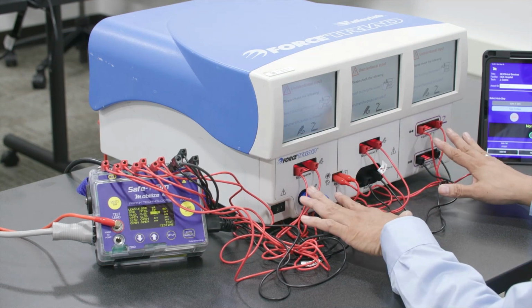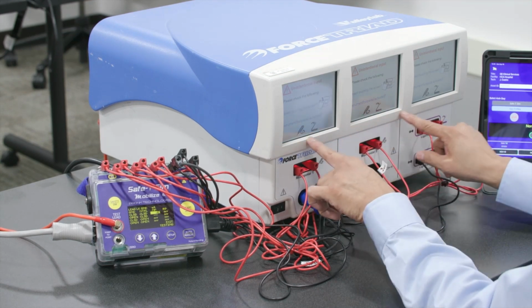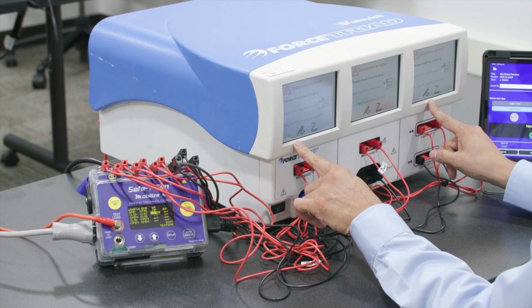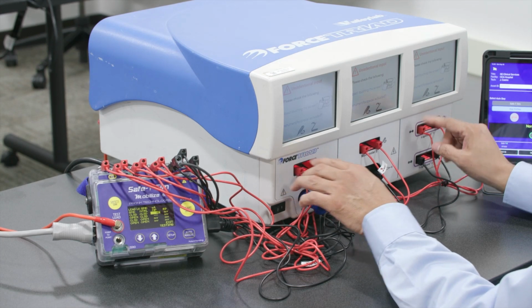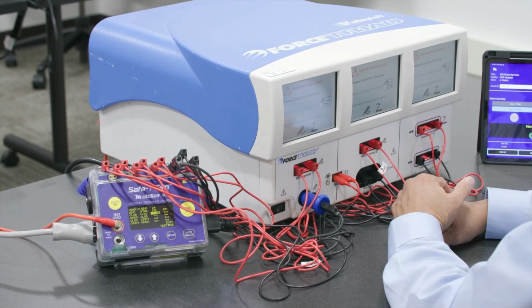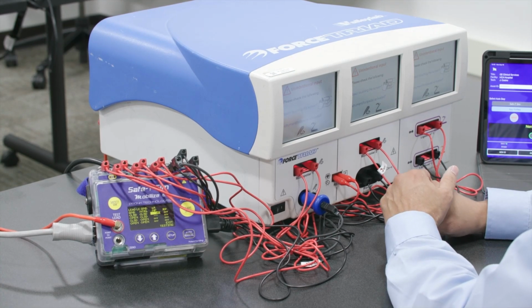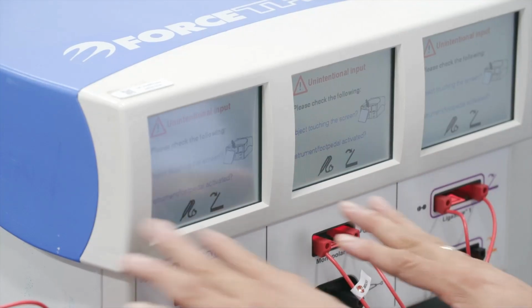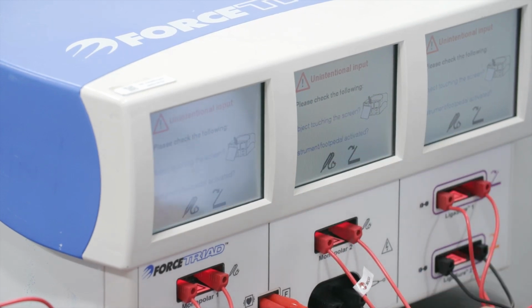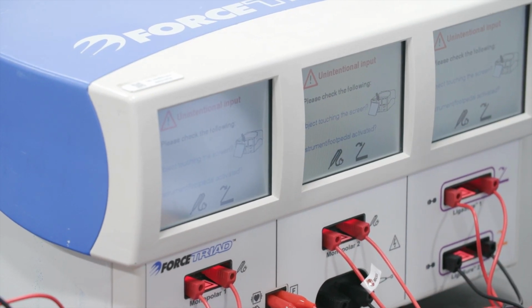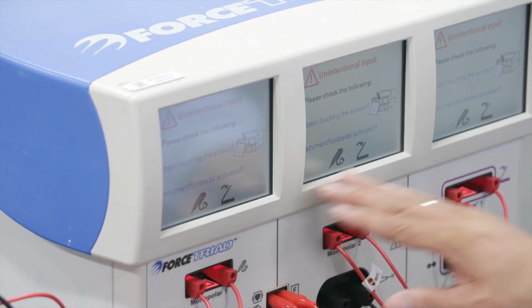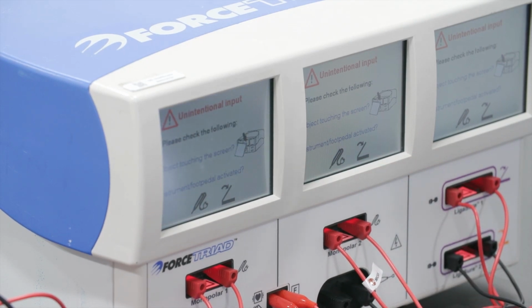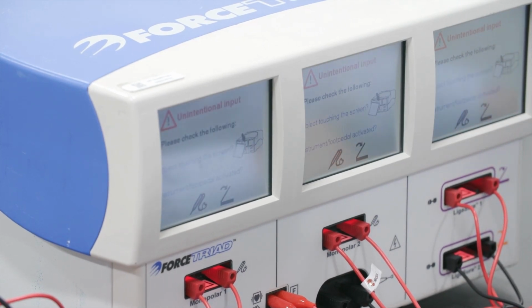Now, when we're running our electrical safety tests, you could very well see this message on the screen. It's an error message that comes up because we've connected all these to the safety analyzer, so it thinks we've activated the touchscreen or the foot pedal. This is normal. It's not an error with the analyzer. It will not impact our electrical safety measurements if you see this message on the screen here. So you could just continue to do the test.